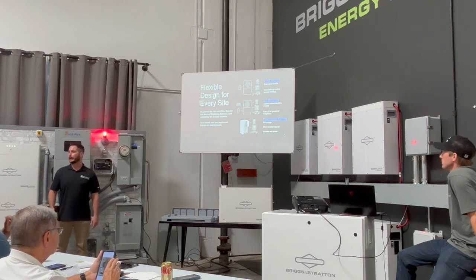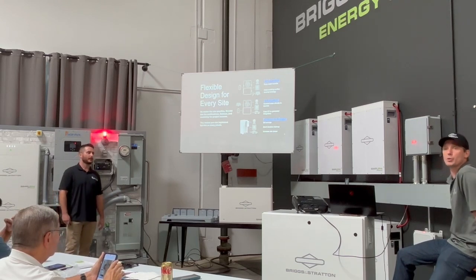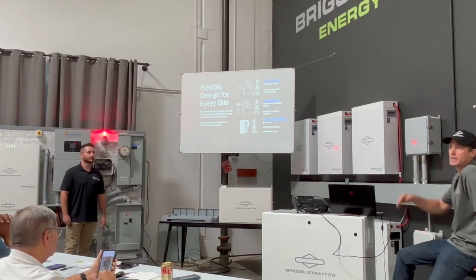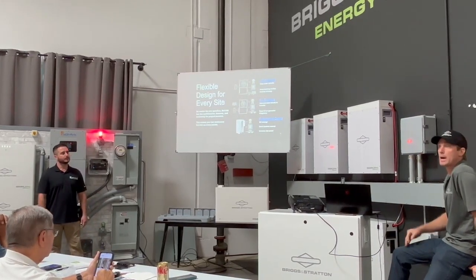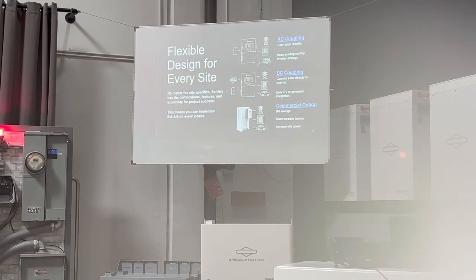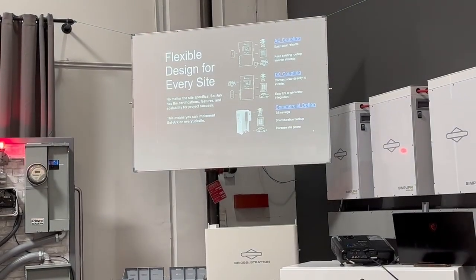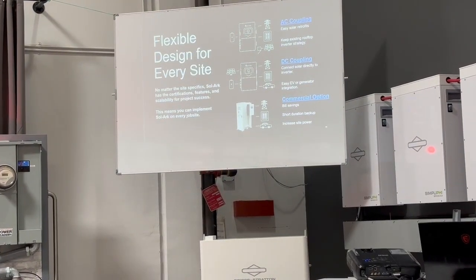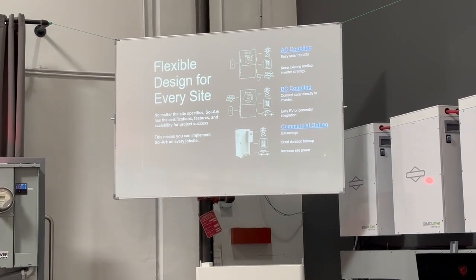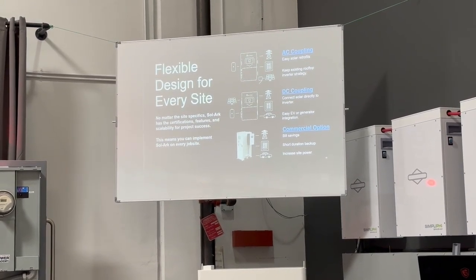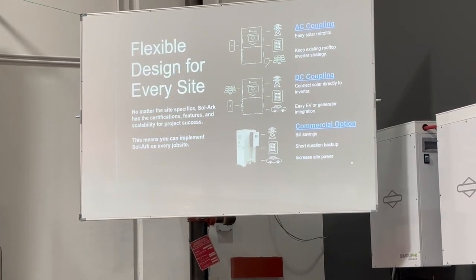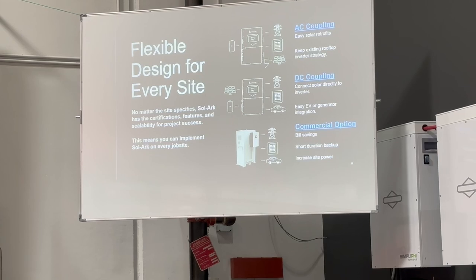DC coupling is pretty much the norm, but you can go either direction, and you can do both. There's no reason you can't, say you go to a job site with 8 kilowatts of AC coupled Enphase already on the roof, but they want to add more solar. You could bring that 8K in through the Sol-Ark, but simultaneously bring 3 more arrays through the DC side on the Sol-Ark, so you have some AC coupled and some DC coupled. Even if you don't install all Sol-Arks on your jobs, the more educated you are with Sol-Ark and our battery partners, it's going to make a lot of jobs much easier to move forward with.